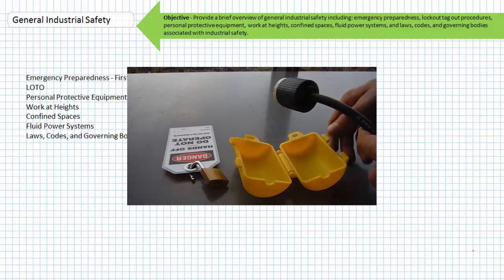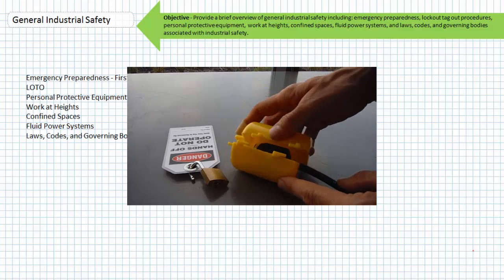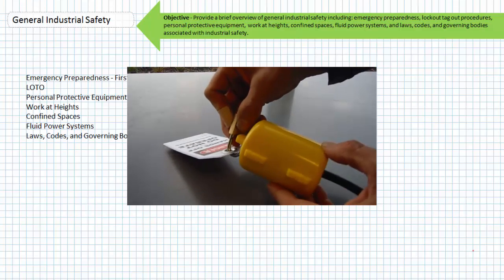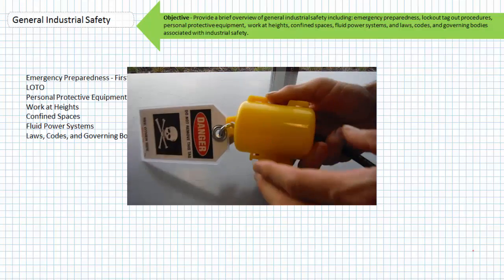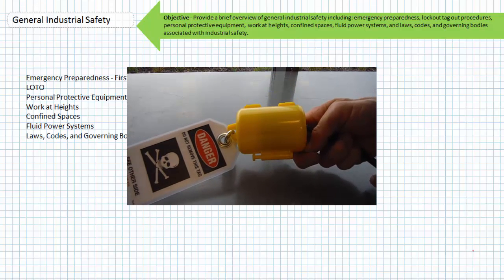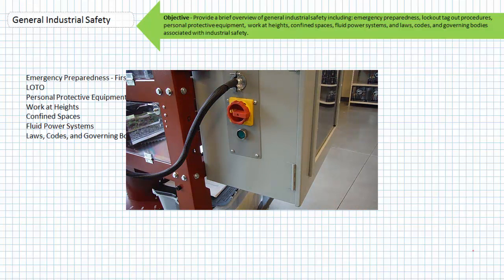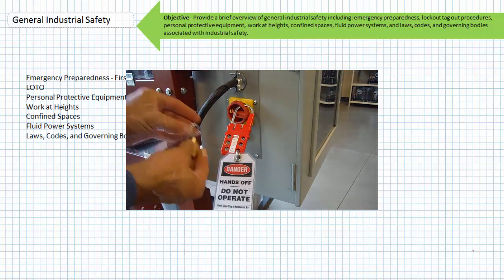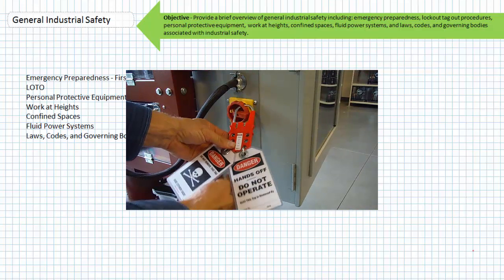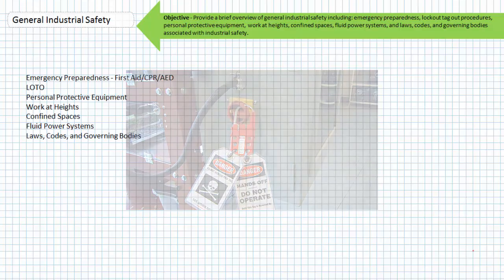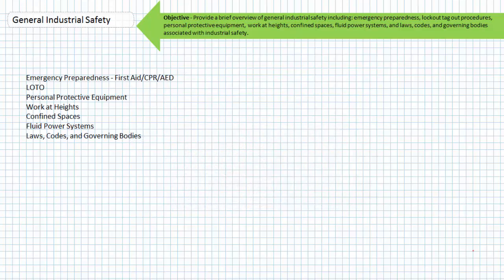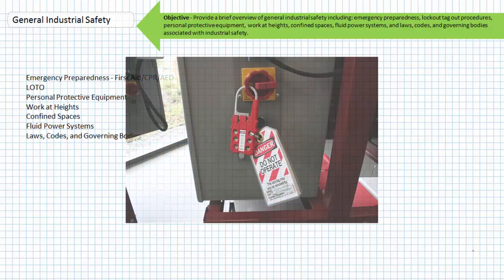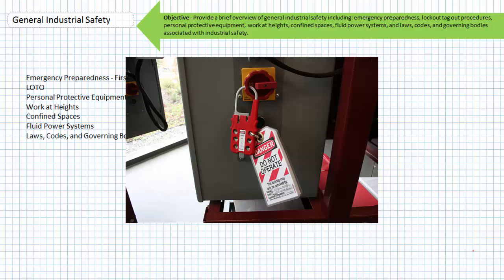Here's a lockout device being used on a plug and another lockout device being used on a switch. All individuals working on that system have their own individual lock. In order to unlock it, all individuals must be present and accounted for. This prevents the undesirable circumstance of leaving a co-worker inside a machine before it's returned to service.